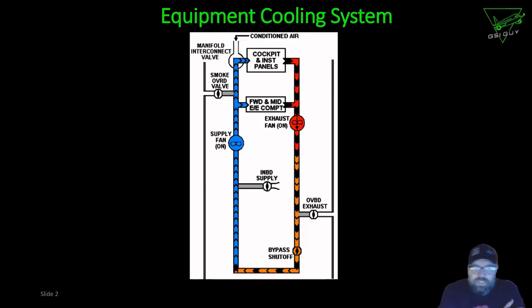So if we take a look at our equipment cooling system, it's a pretty simple system. I know people get twisted on the lights and what comes on and what turns off. I'll walk you through it. It's not hard. This is a general breakdown of the equipment cooling system and what's in it. We have three valves, technically four valves. We have our bypass shutoff located right here. We have our inboard supply that brings air into the system, the smoke override valve, and the overboard exhaust valve. We'll talk about what those do when we get into some of the non-normals of the system.